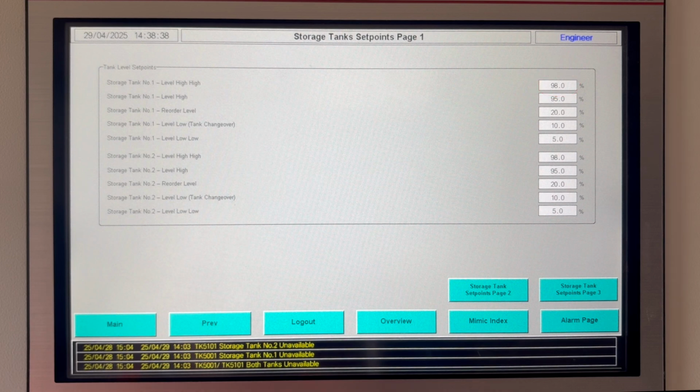The tank would overflow after a further 2,400 litres. Reorder level. This will produce an event alarm, alerting ops to the fact that an order needs to be placed for more chemical. This was set at 20% at commissioning on the understanding that the reorder amount will be 17 tonne, 10,750 litres.